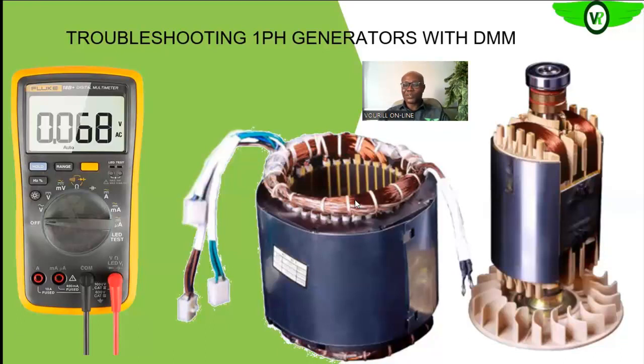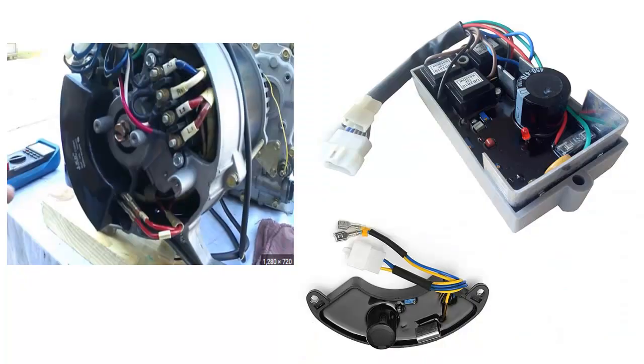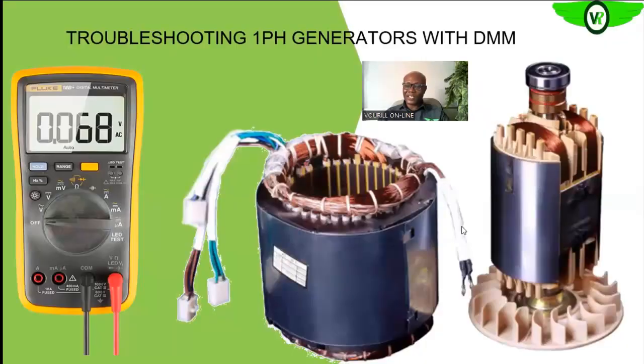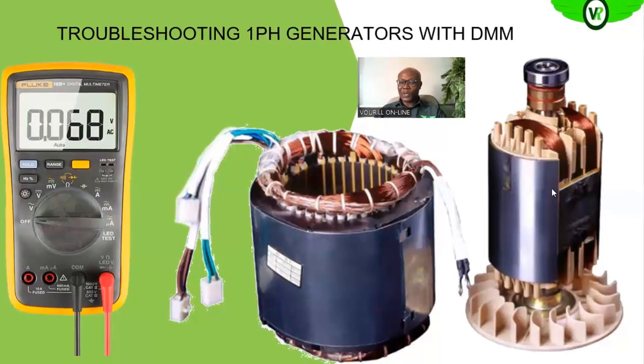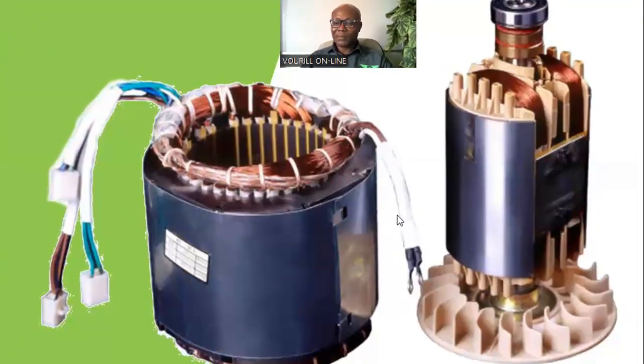Then on the terminal block, you have your rectifier or your AVR that supplies this main feed. These are the terminals of the exciter winding, the exciter armature. It's the same field winding that induces voltage into the exciter armature, but it's a separate winding wound on this stator. So the output is sent to your AVR or your rectifier, and then the DC output from the rectifier is sent by this slip ring to the main field. As it's rotating, that will magnetize the main field, and it will induce voltage on the main armature of the generator, and then you get your output, where you can tie your load to.